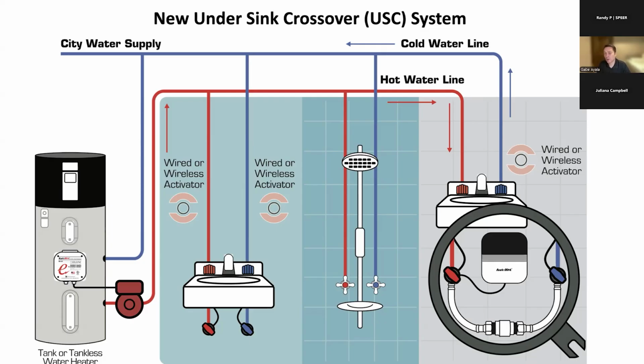It's called the undersink crossover. We call it the USC for short. Essentially, what this does is it uses your existing plumbing to create on-demand recirculation. So how does it work? The pump is located back at your water heater. Let me get my little laser pointer here. Okay, so your pump is going to be located back at your water heater, and that's where the controller is too. And then you want to identify the fixture that is the farthest off the line.